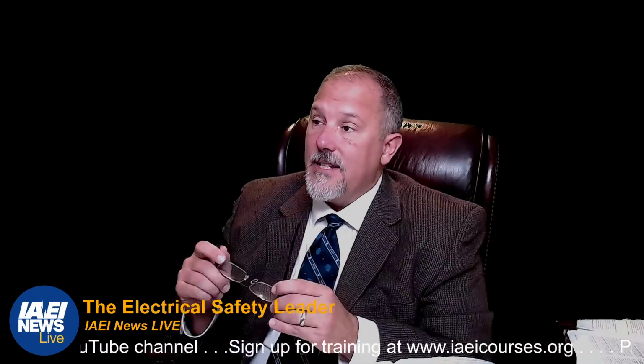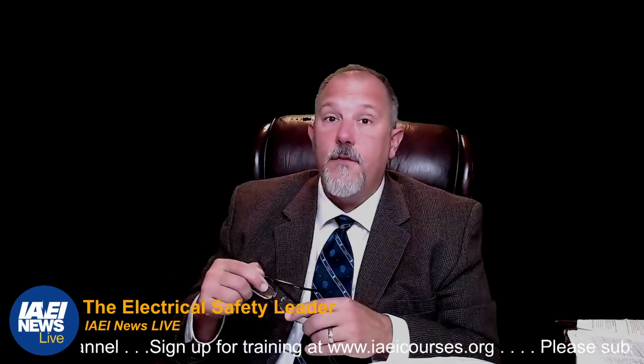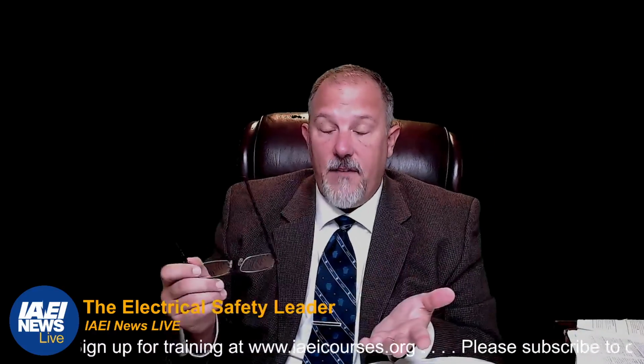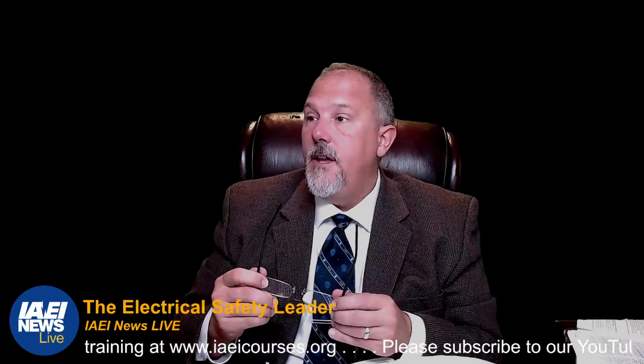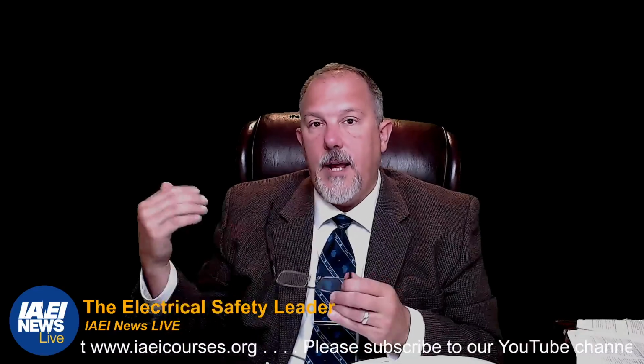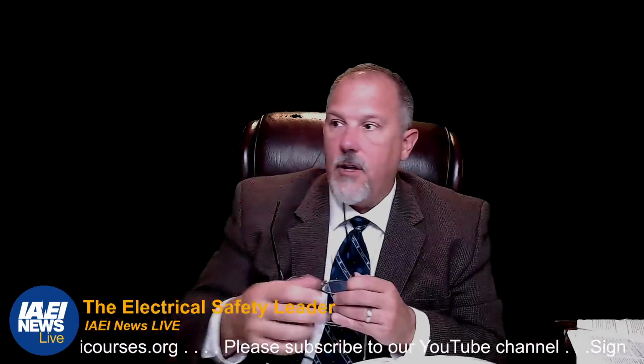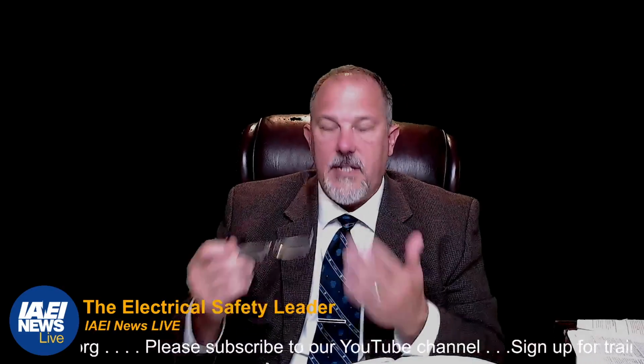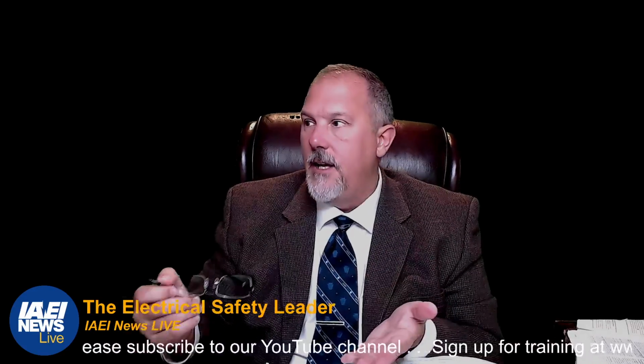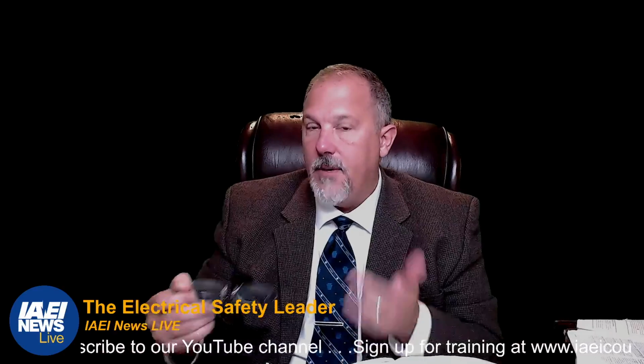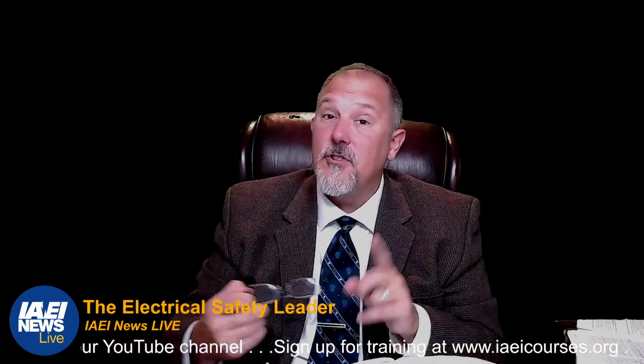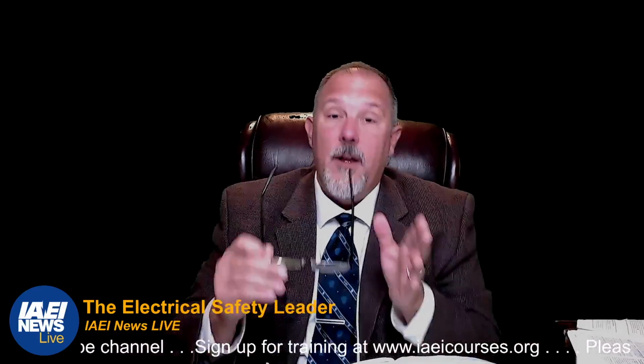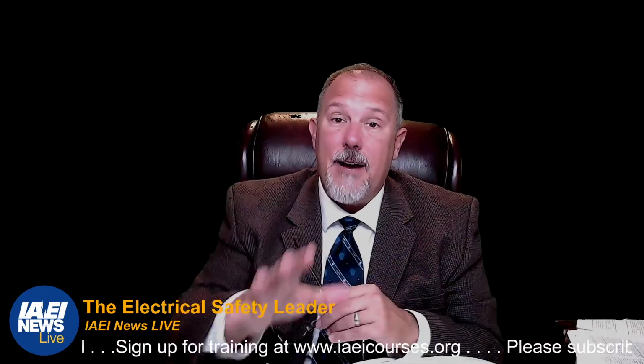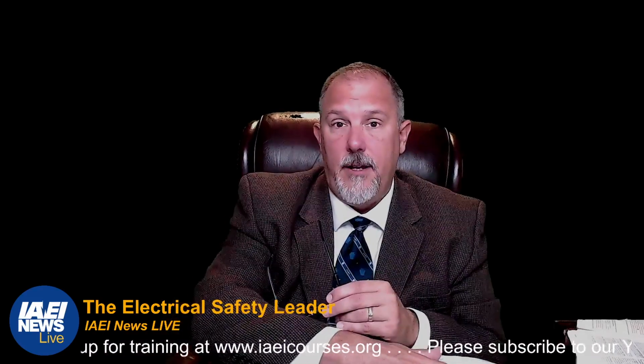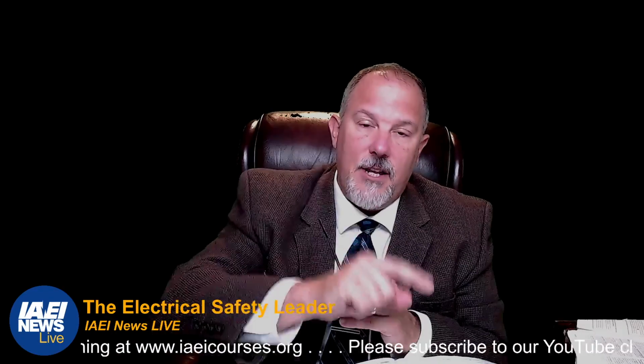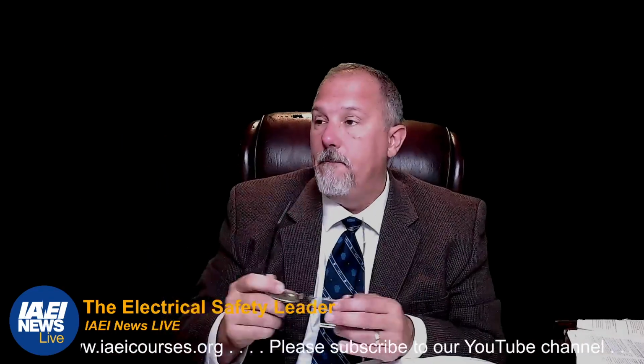So, panel boards listed for the specific enclosure. If I have a single manufacturer that's listed for that enclosure, then if you take a panel board and put it into that enclosure, you'll retain the short circuit current rating of that equipment. But remember, it's going to be dependent upon the breakers that you put in it. Remember, the manufacturer gives you a recipe on how to determine the short circuit current rating based upon the overcurrent devices that you place in it or what's upstream.